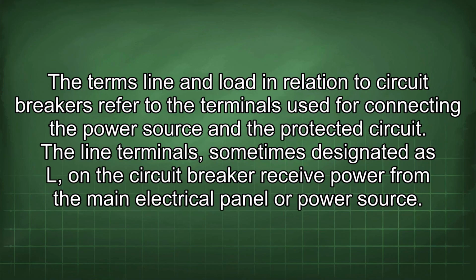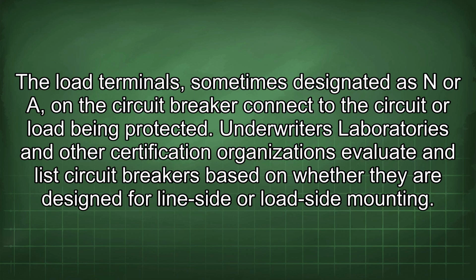The terms line and load in relation to circuit breakers refer to the terminals used for connecting the power source and the protected circuit. The line terminals, sometimes designated as L, on the circuit breaker receive power from the main electrical panel or power source. The load terminals, sometimes designated as N or A, on the circuit breaker connect to the circuit or load being protected.